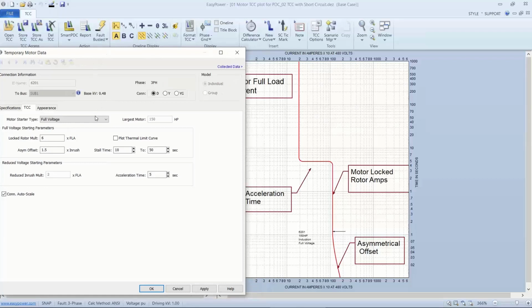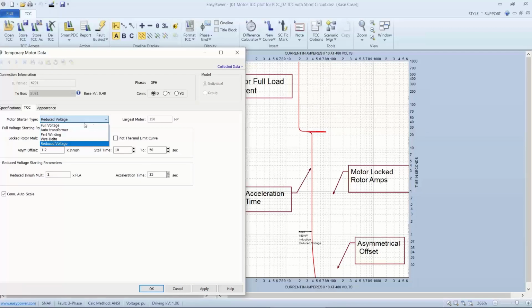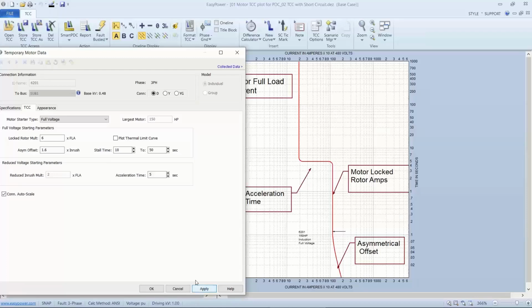So first of all, we're plotting a full load across the line starting current. If we looked at a reduced voltage, which might be a soft start or another type of starter, we would see a different shape plot, a lower current for the locked rotor multipliers. Again, the locked rotor multiplier is a function of some multiple of full load current, and if we used a different one, it will change the shape of our motor curve, and affect the protective device settings that we're going to be ultimately trying to achieve. So let's take that back to 6.